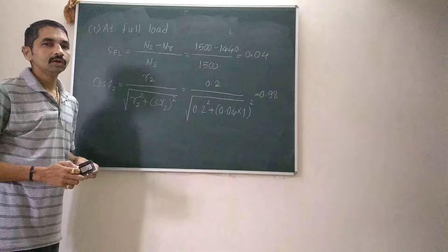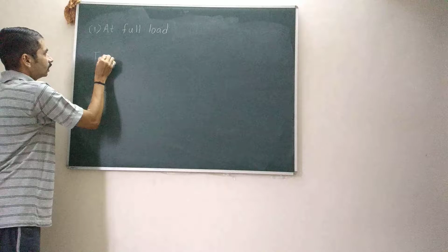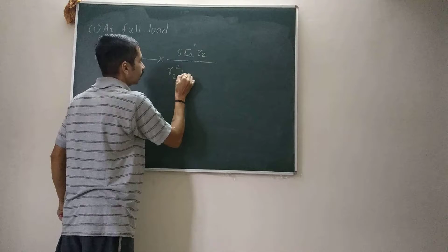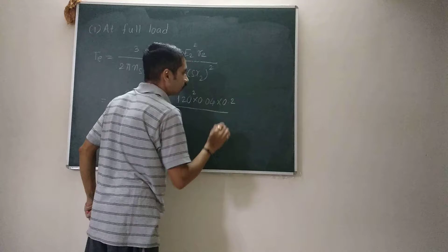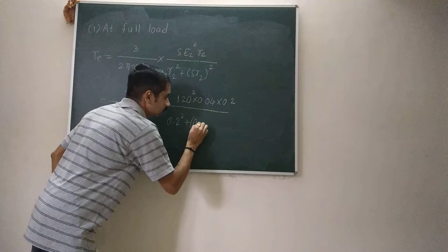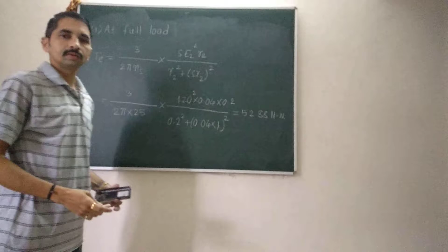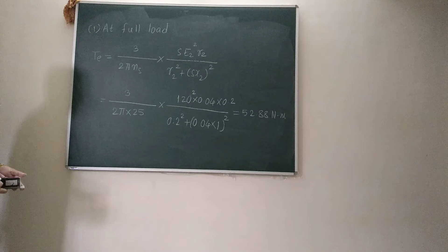Okay, let us try to get now the torque at full load condition. As we have seen earlier, the expression for torque at full load is given as Te is equal to 3 over 2 pi Ns multiplied by s E2 square R2 divided by R2 square plus (sX2) whole bracket square. Now I will just substitute the values in this equation. So it will be 3 over 2 pi into 25, which is the value of synchronous speed in RPS, multiplied by E2 square, that is 120 square, multiplied by 0.04 multiplied by 0.2 divided by 0.2 square plus (0.04 into 1) whole bracket square. If I solve it further, I am getting the value of my torque as 52.88 Newton meter. So please check whether you are getting the same answer or not. Okay, is it fine?